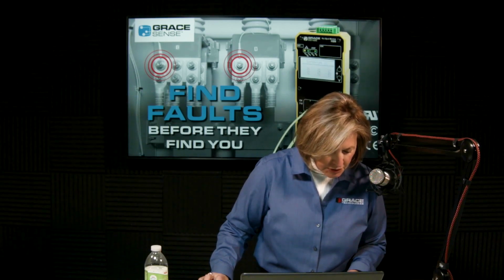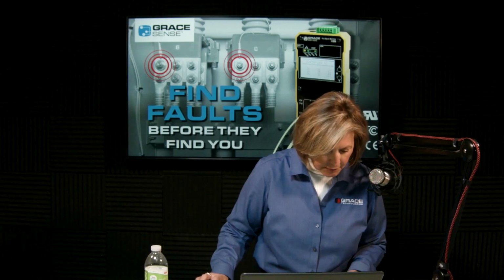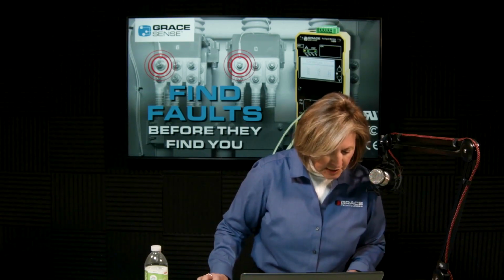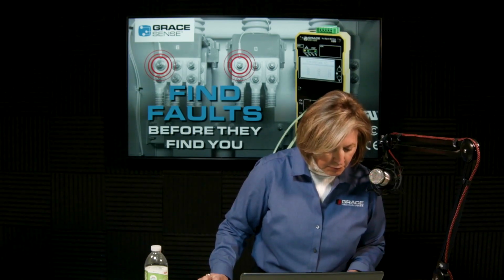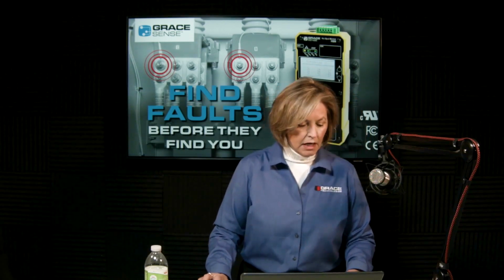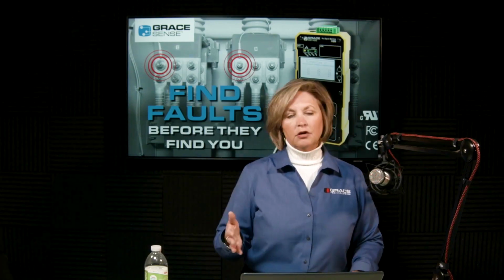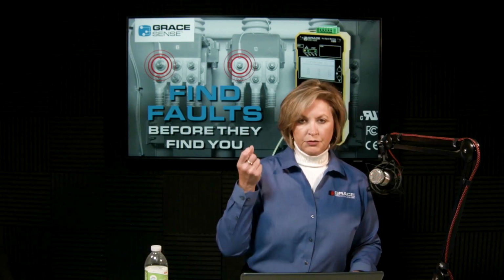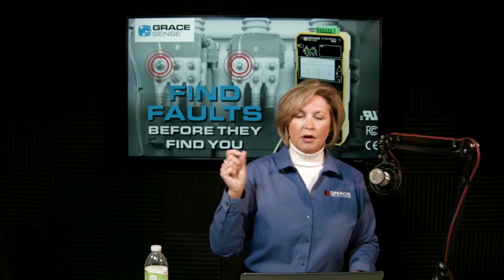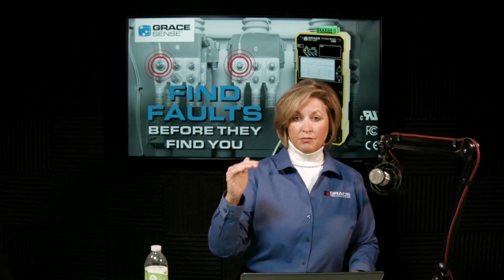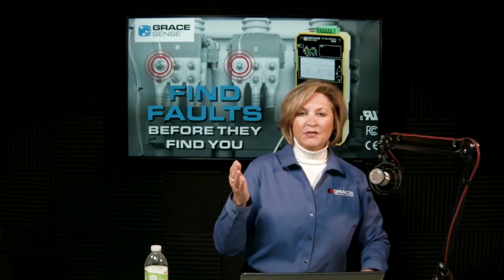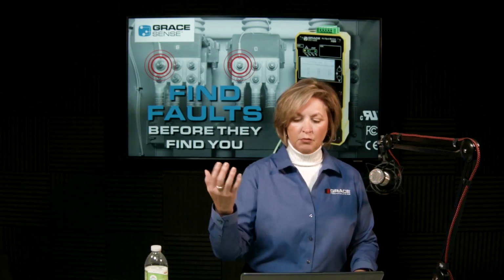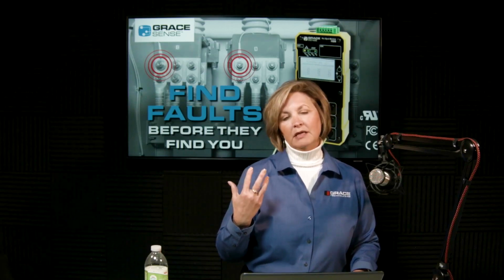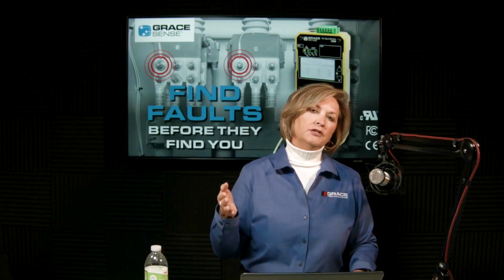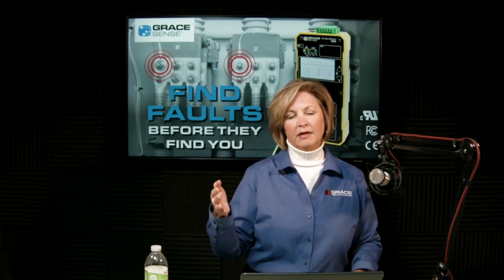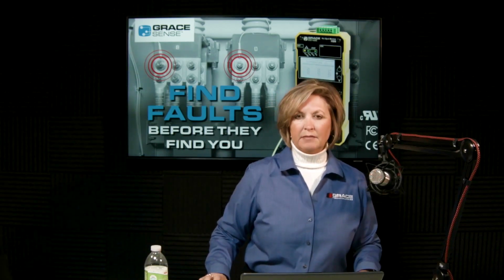Is there a relay changeover contact? Is the relay a changeover contact? Can we get signal green for good and red for problem? Well, on this particular HSM unit, the internal relay contact will close upon any of those points in that unit reaching the first threshold. So the end user can choose to do red green. This particular unit would be mounted inside the instrument compartment, and therefore maybe even not be seen. So we want to address that with all the mapping that's coming from the HSM unit into a secondary system, or like your power management system.